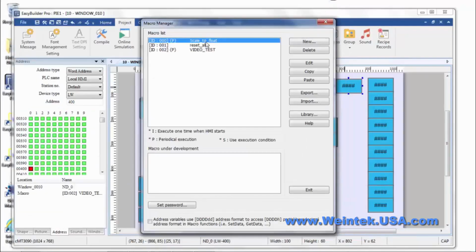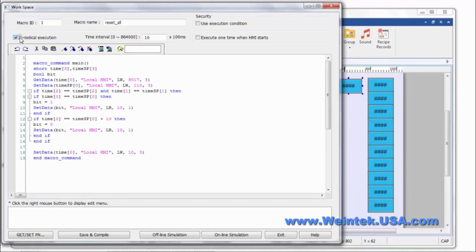I did a little scheduling type macro here. We're actually reading the HMI time into the system here. It's an array of 3. And this is the starting register. This is actually seconds, and 18 is minutes, and 19 is hours. So we're doing a little comparative statement here, and you'll also notice I'm doing a read here. I've got set points that I can define for when this scheduler, if you will, does its thing.